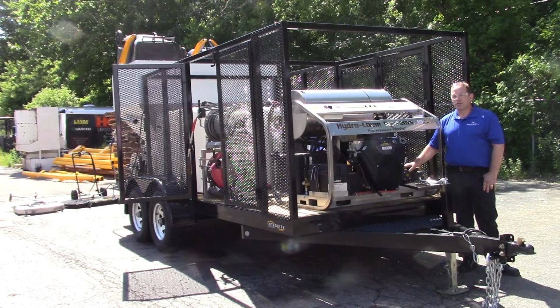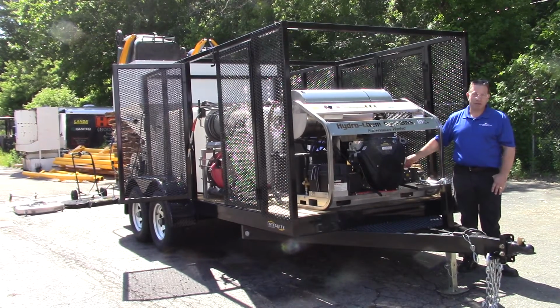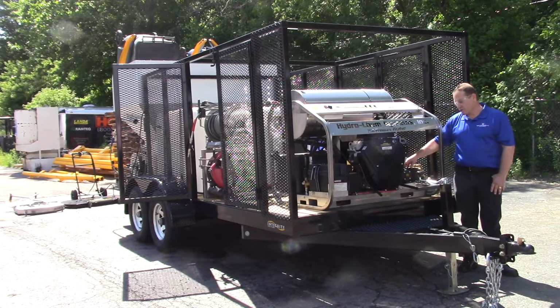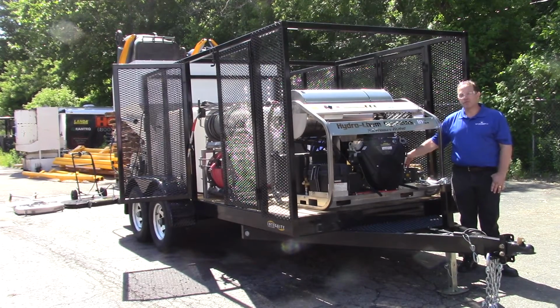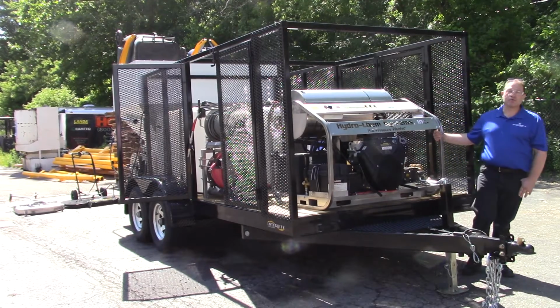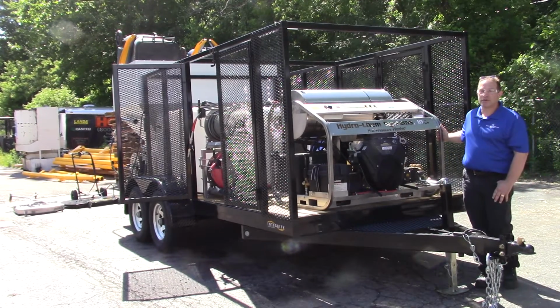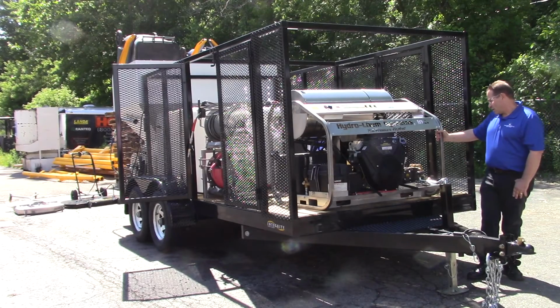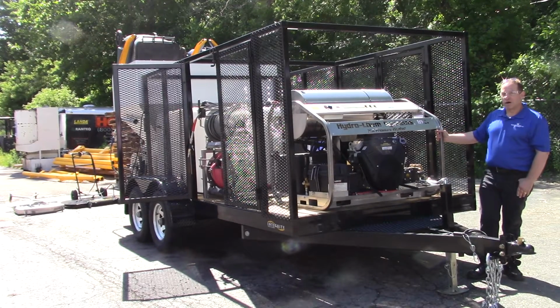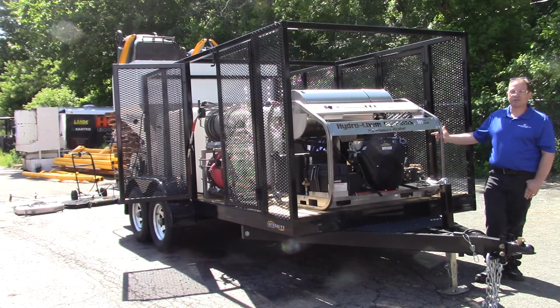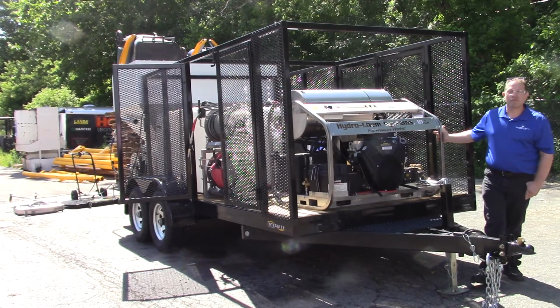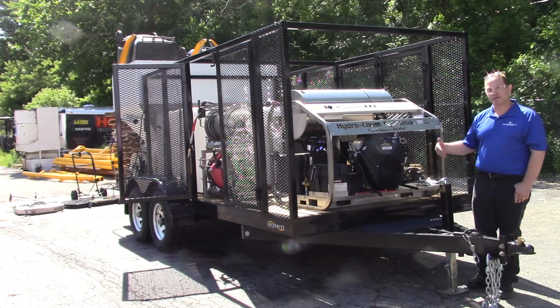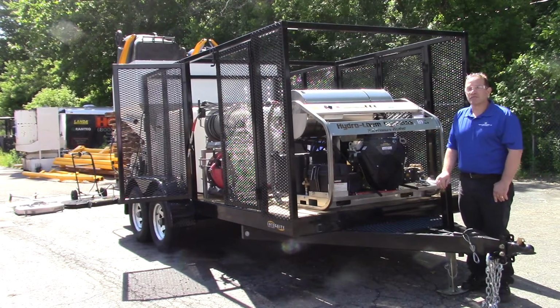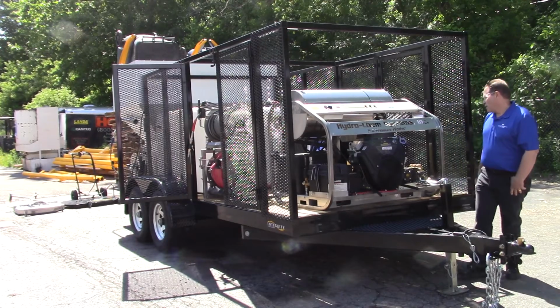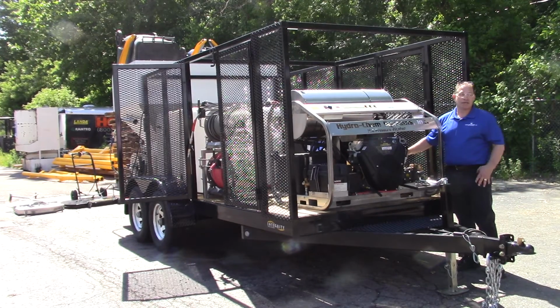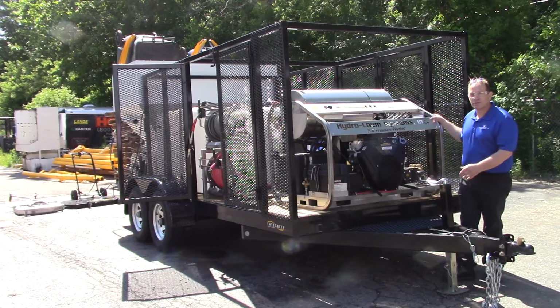The pump uses normally a 30 weight hydraulic oil or pump oil on that, and that also should be maintained. They say up to 300 to 500 hours. I still like going overboard on that to keep it between 100 and 300 hours on that. It is a belt-driven pump, belt-driven generator, so anytime there's issues with low pressure, low voltage, to keep it simple, technique is to look for the belts, start from that point and move your way out. They got split belt guards, so it's easy to do your belt changes within reason.